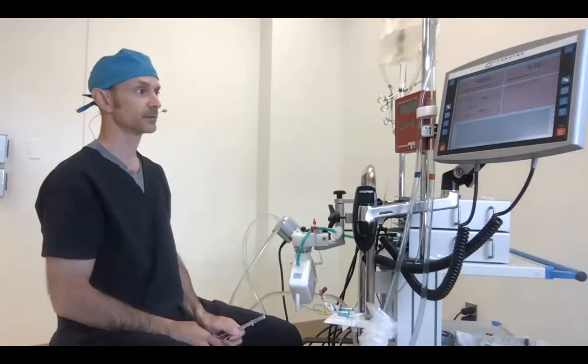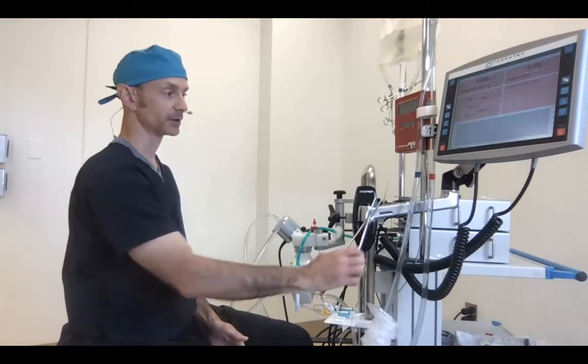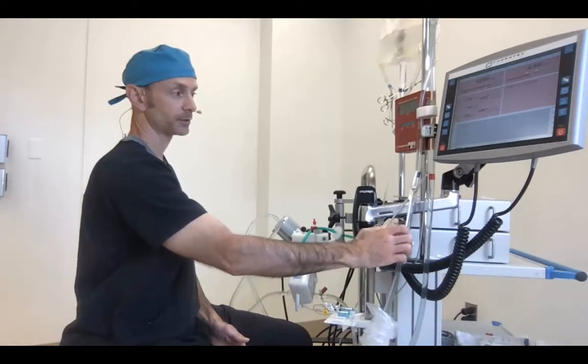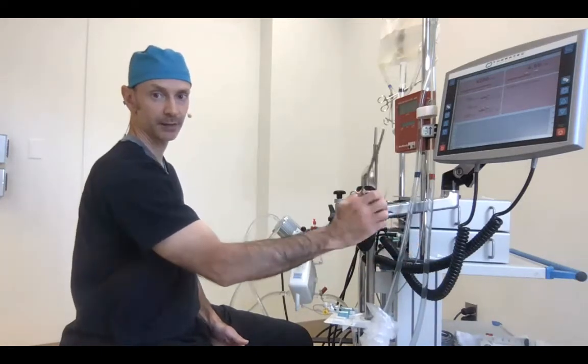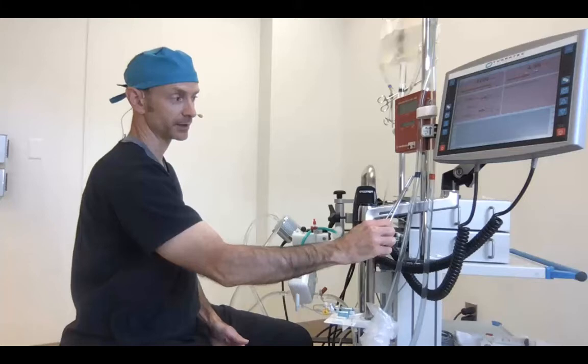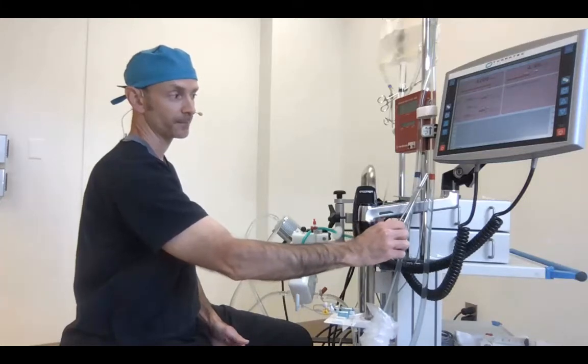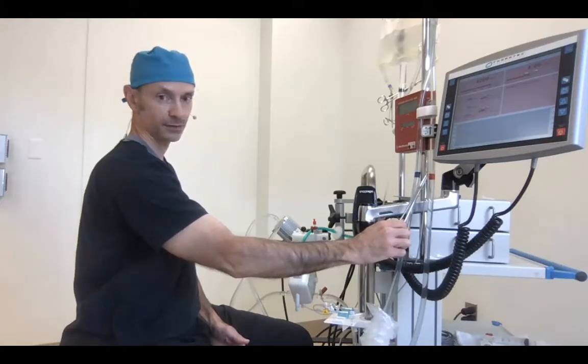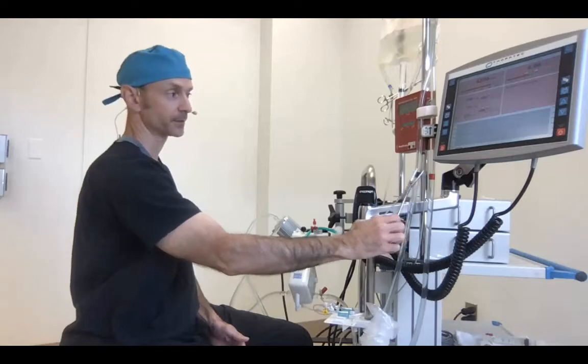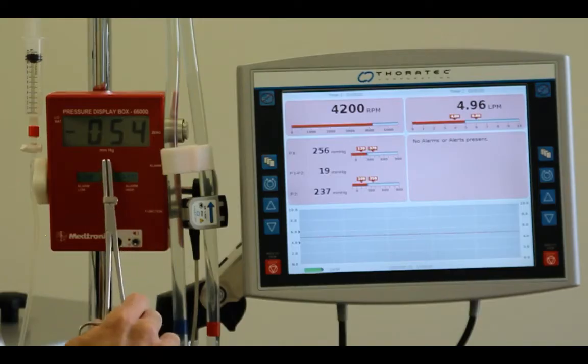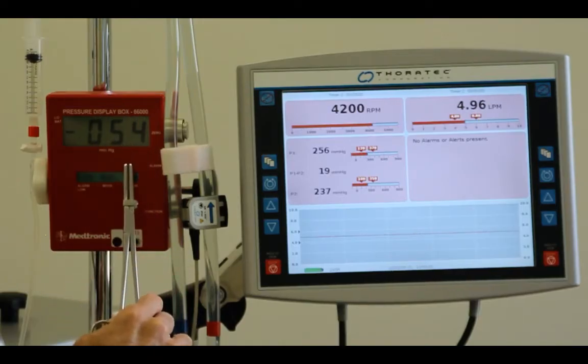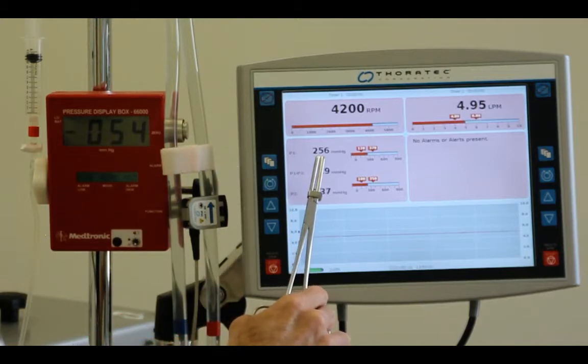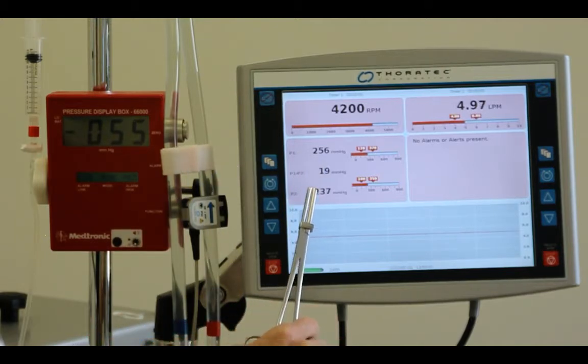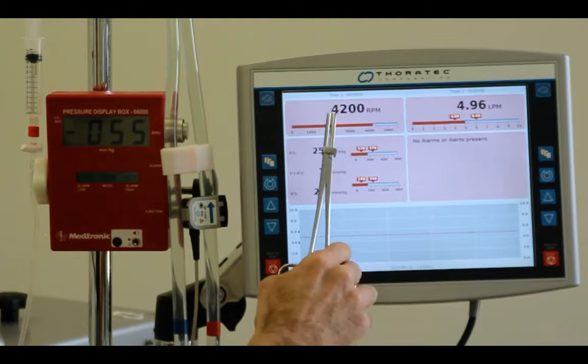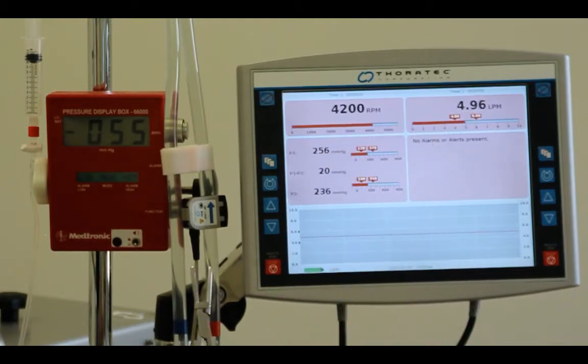So let's demonstrate then what happens when we cause preload problems or afterload problems, and we're going to simulate that by placing a tubing clamp on either the inlet to the pump or the outlet, the arterial line of the circuit, the outlet of the entire circuit. So here let's note our pressures. We're at -50 on the venous line, 250 and 230 on your pre and post membrane pressure at 4,200 RPMs and just about 5 liters of flow.